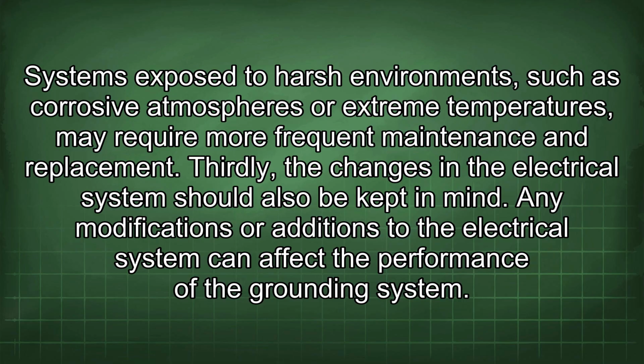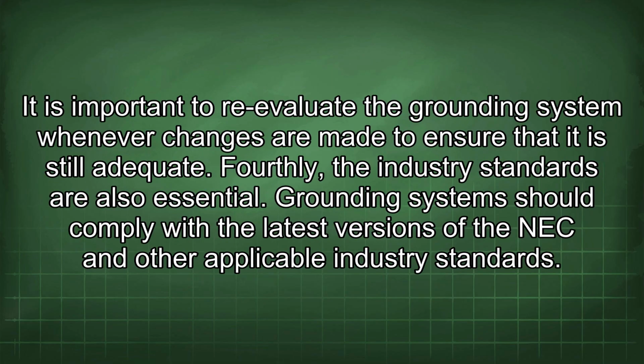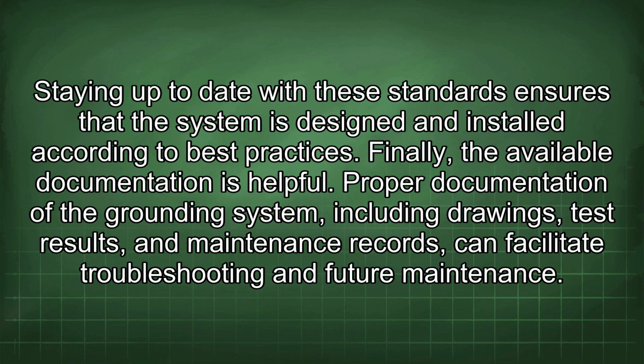Thirdly, the changes in the electrical system should also be kept in mind. Any modifications or additions to the electrical system can affect the performance of the grounding system. It is important to re-evaluate the grounding system whenever changes are made to ensure that it is still adequate. Fourthly, the industry standards are also essential. Grounding systems should comply with the latest versions of the NEC and other applicable industry standards. Staying up to date with these standards ensures that the system is designed and installed according to best practices. Finally, the available documentation is helpful. Proper documentation of the grounding system, including drawings, test results, and maintenance records, can facilitate troubleshooting and future maintenance.